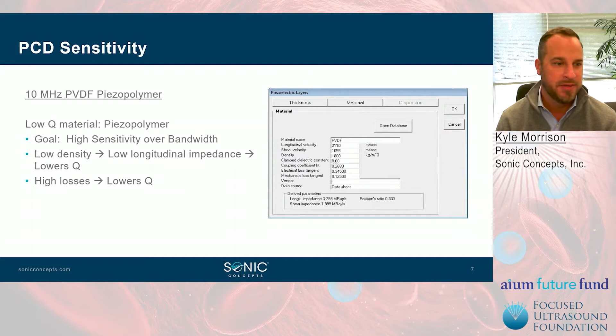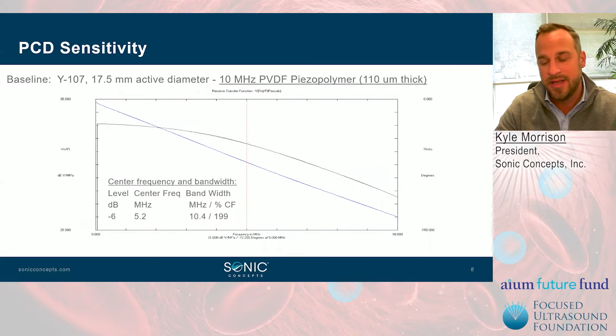So here's an example of a received transfer function. Notice that from 0 to 10 megahertz, we're within 6 dB. And so we're at 17.5 millimeter diameter. That's a lot of aperture. So we're able to get about 38 volts per megapascal, 31.6 dB volts per megapascal. To compare that with a 200 micron needle hydrophone, this is 3,000 times more sensitive, or 70 dB more sensitive. So this really helps with SNR, and really we become less reliant on a preamplifier.